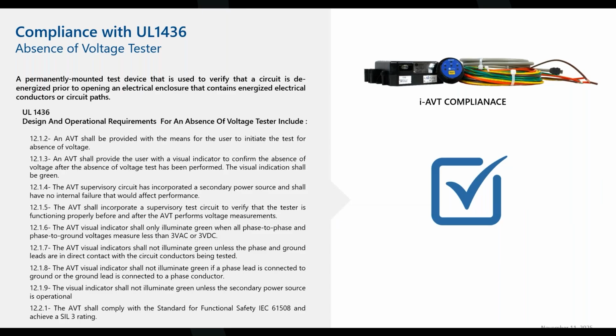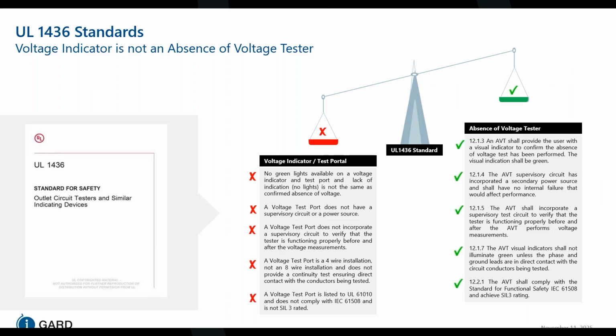An absence of voltage tester is a permanently mounted device that verifies a circuit is truly de-energized before work begins, meeting strict UL 1436 and IEC 61508 standards. It provides a green visual indication only after confirming the absence of voltage, uses a supervisory circuit and secondary power source for reliability, and prevents false signals. With SIL3 safety integrity, AVTs deliver accurate, fail-safe verification, far superior to simple indicators, protecting workers from shock and arc flash hazards. Voltage indicators and test portals are often mistaken for the tools that confirm the absence of voltage, but they do not meet the safety requirements for this critical task.